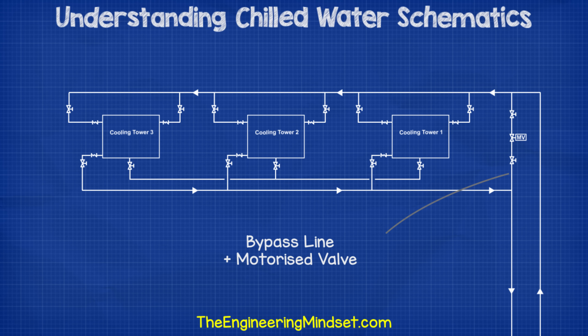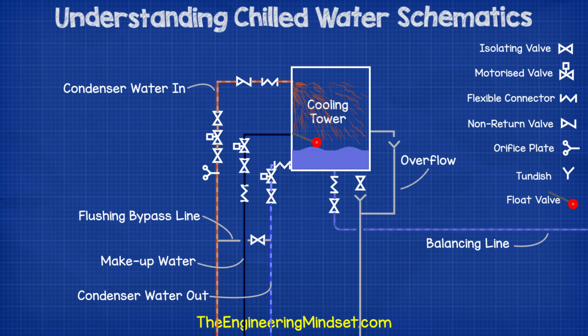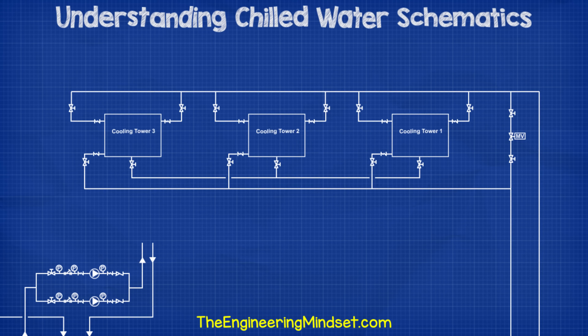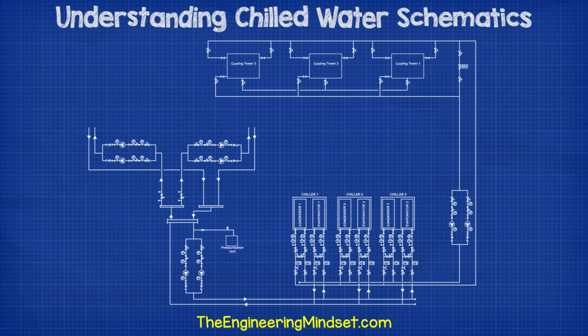There might also be a bypass line with a motorized valve across the cooling towers' flow and return lines. This can have various functions such as maintaining a minimum flow rate and also protecting the chiller from tripping on low and high pressure due to the temperature of the return condenser water being out of design limits — for example, during startup on a cold winter morning. Another common version for the cooling tower you might come across has the flow and return lines for the condenser water, a balancing line between other cooling towers, a makeup line which tops up the water if the level gets too low, and an overflow with a drain line. Some will have a flushing line between the flow and return lines for system cleaning. If you want to know how cooling towers work, we've covered this in a previous video — links are in the video description below.